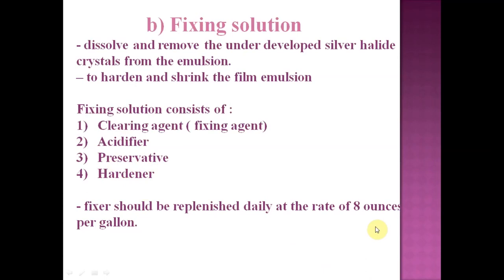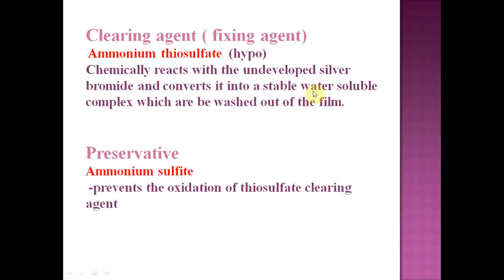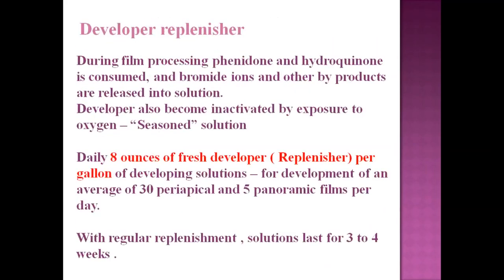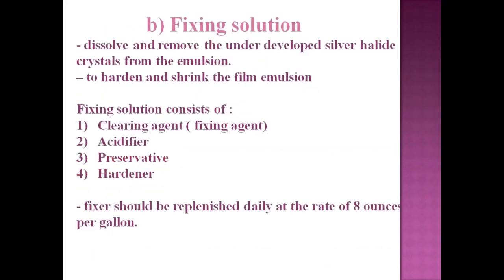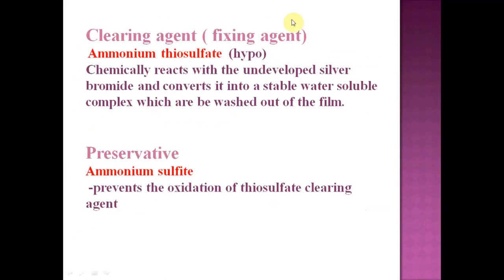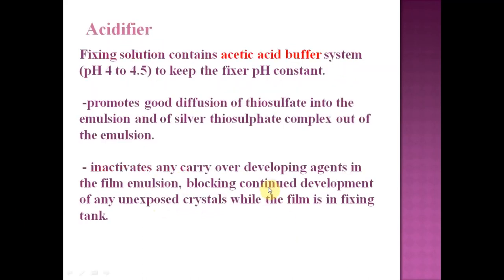The fixing solution consists of a clearing agent (fixing agent), acidifier, preservative, and hardener. The clearing or fixing agent is ammonium thiosulfate, which chemically reacts with the undeveloped silver bromide and converts it into a stable, water-soluble complex that is washed out of the film. The preservative is ammonium sulfite, which prevents oxidation of the thiosulfate clearing agent.